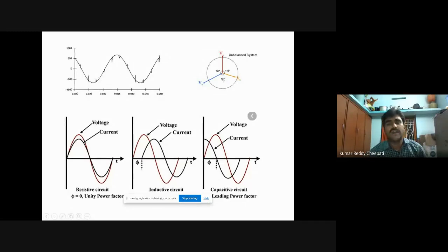And this is the diagrammatic representation of an unbalanced system, where we can see a phasor unbalance is happening. Ideally, the phase angle between two phases must be 120 degrees. Here is a phase angle unbalanced system. Because of this unbalanced system, there is a flow of neutral current to the ground. The neutral conductor gets heated up. That is the drawback of an unbalanced system. And the lowering of power factor.